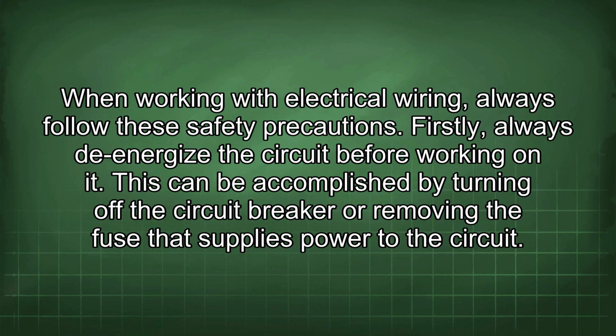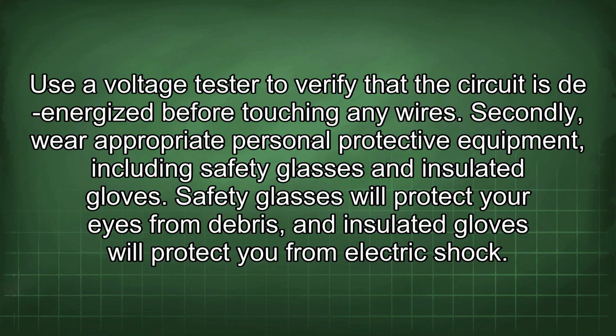When working with electrical wiring, always follow these safety precautions. Firstly, always de-energize the circuit before working on it. This can be accomplished by turning off the circuit breaker or removing the fuse that supplies power to the circuit. Use a voltage tester to verify that the circuit is de-energized before touching any wires. Secondly, wear appropriate personal protective equipment, including safety glasses and insulated gloves. Safety glasses will protect your eyes from debris, and insulated gloves will protect you from electric shock.